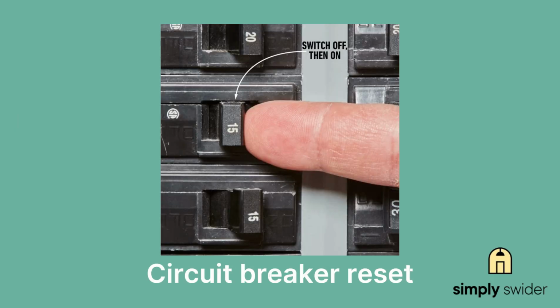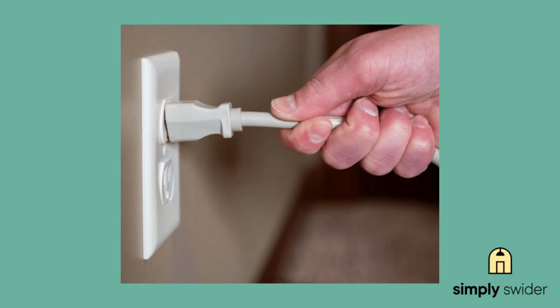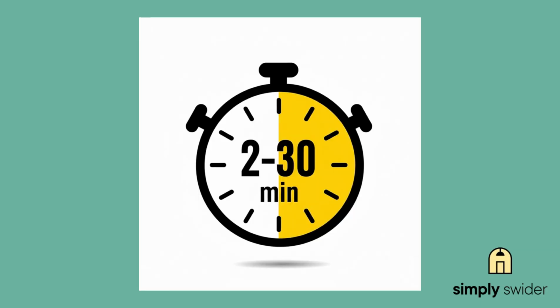Sometimes it's just a temporary electronic hiccup. Power surges or internal logic errors can trigger a false F10 code out of nowhere. The code shows up suddenly but might not come back right away after you restart everything. Before you start tearing into your oven, try this simple fix. Unplug the unit or flip that circuit breaker for anywhere from 2 minutes up to half an hour. This hard reset clears out any glitches in the control board's memory.